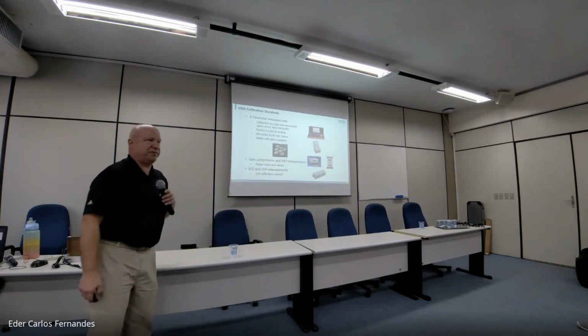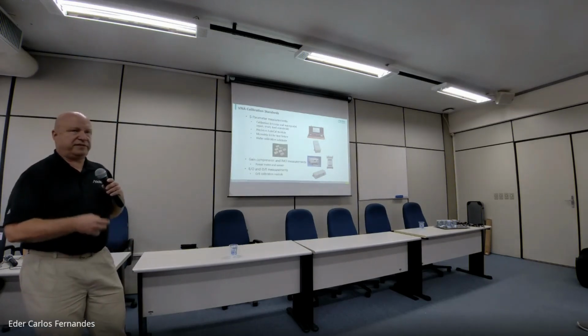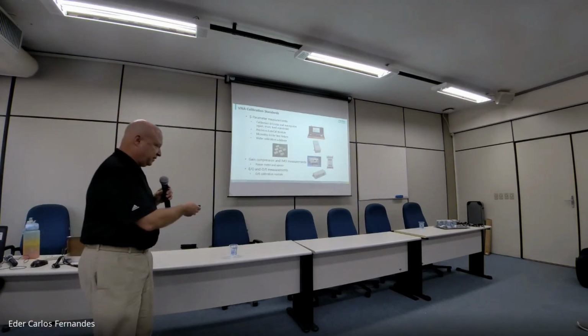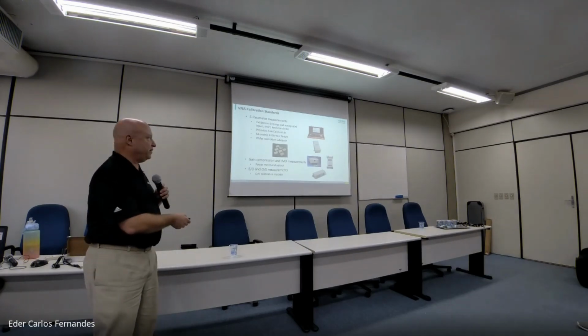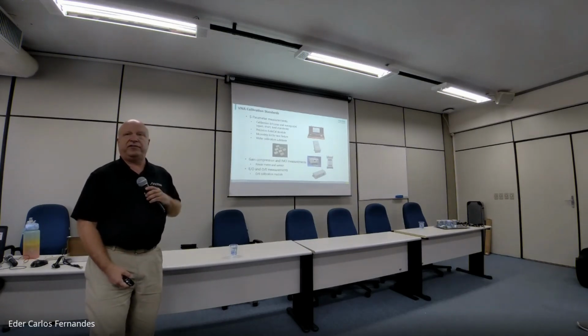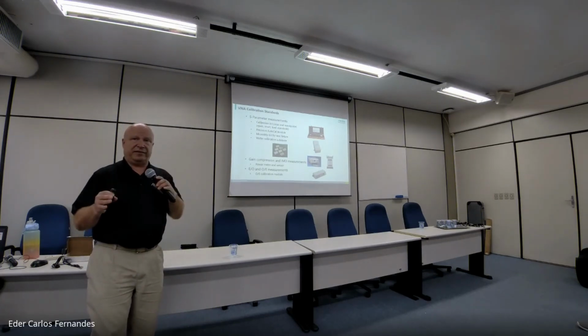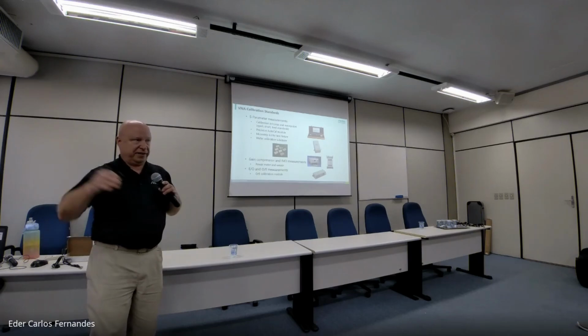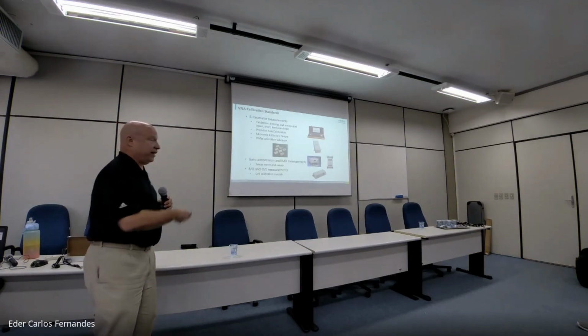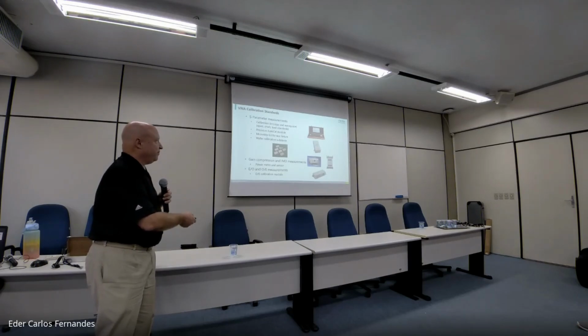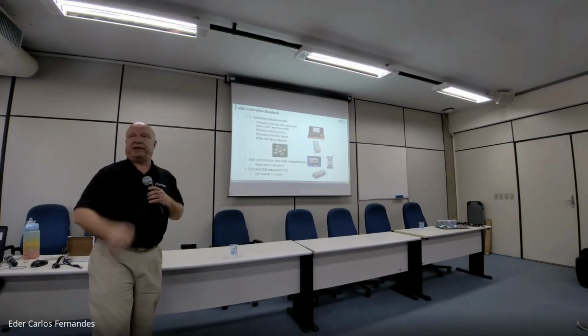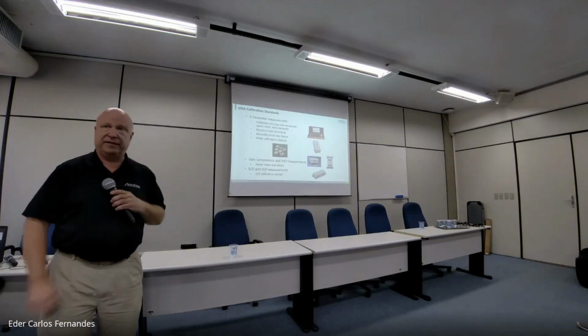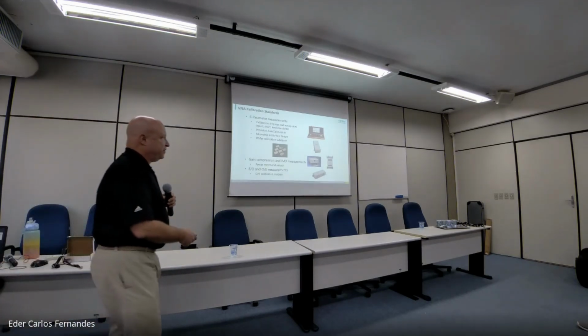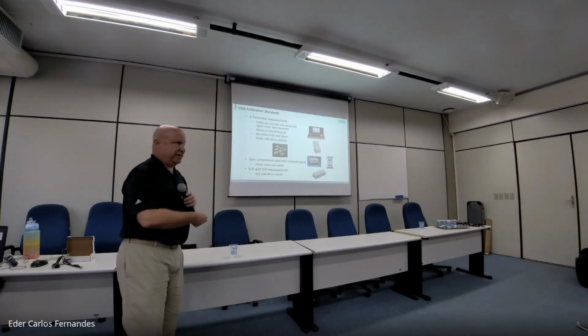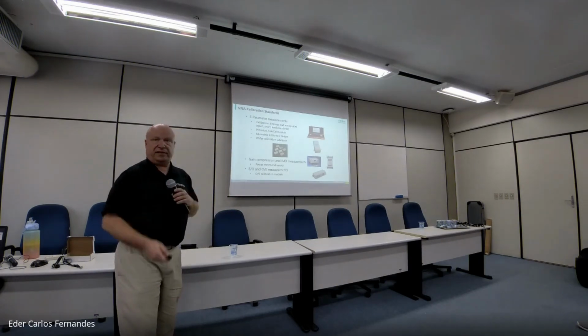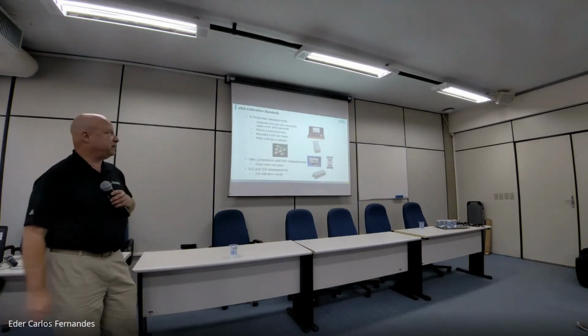Finally, E to O and O to E measurements require an O to E reference. You need some way to be able to separate E to O and O to E, and the only way to do that is to have a reference for one or the other that you can remove when you're measuring the two together. Because the VNA is going to start with electrical and end with electrical, but in between you could have an E to O and then an O to E. I need to know what the response of one or the other is so I can effectively remove it and make a measurement of the opposite device, isolating it to what you want to measure. The O to E module provides that reference because it's a characterized photodiode that has magnitude and phase information up to as high as 110 gigahertz. So we use that as our reference.